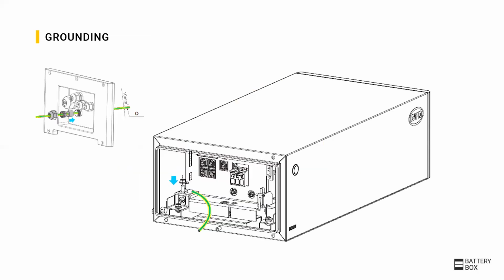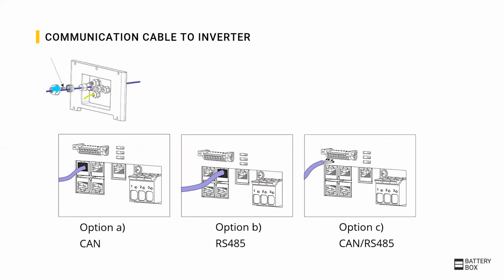First, connect the ground cable. It is important to connect the battery directly to the ground of the house. Do not connect the battery ground to the inverter ground, as this might lead to communication problems. Next will be the communication cable to the inverter.